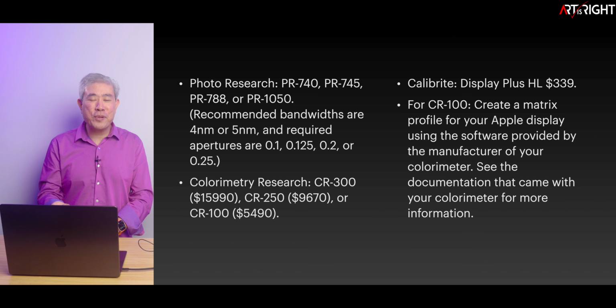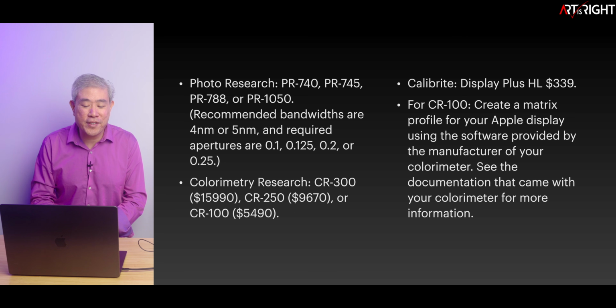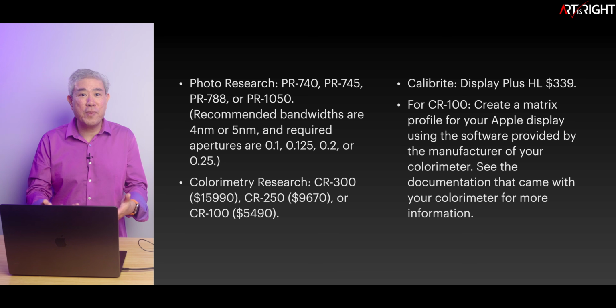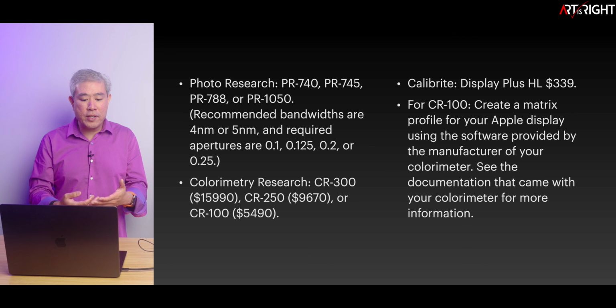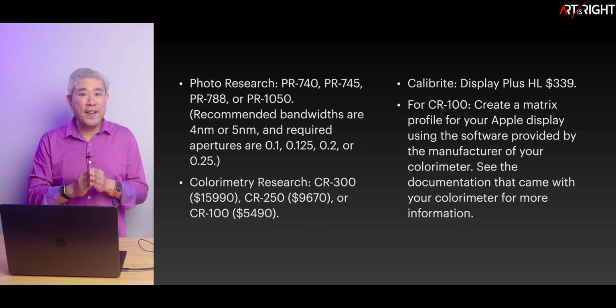But there's also that parenthetical, recommended bandwidth 4 or 5 nanometers, but the aperture as follows. I mean, you need a lot of know-how to use this device. It's not as simple as just plugging in and being able to use it right away. You need to set all these settings up. And then there's another class of device, the Colorimetry Research CR300, which is close to $16,000. The cheapest one on that list is the CR100 at $5,500.